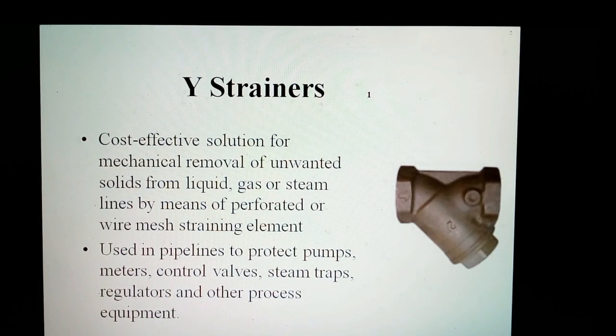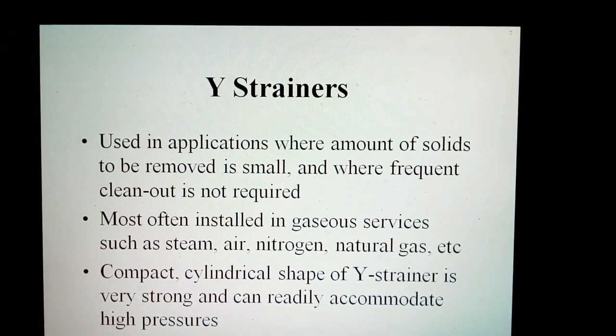Y-strainers are used in pipelines to protect pumps, meters, control valves, steam traps, regulators, and other process equipment. They are typically used in applications where the amount of solids to be removed is small and frequent clean-out is not required. They are most often installed in lines carrying gaseous substances such as steam, air, nitrogen, natural gas, etc. The compact, solid shape of the Y-strainer is very strong and can readily accommodate high pressures common in this type of service. Pressures up to 6,000 PSI are not unusual.